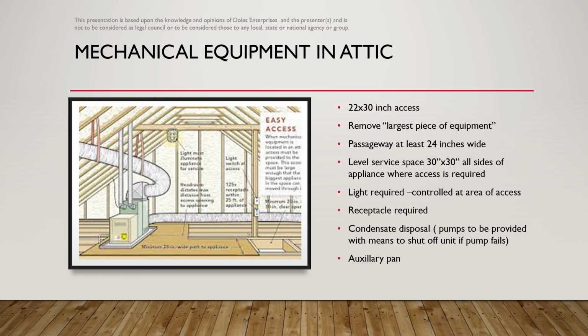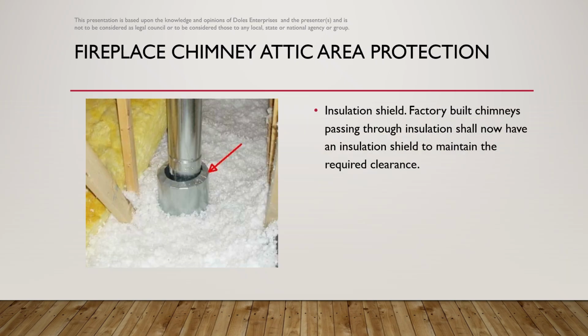A light is required that is controlled near the access opening for the attic area. A receptacle is required for convenience of working on the equipment. Auxiliary pans and condensate disposal are also required by the code. Factory-built chimneys passing through insulation shall now have an insulation shield to maintain the required clearances.